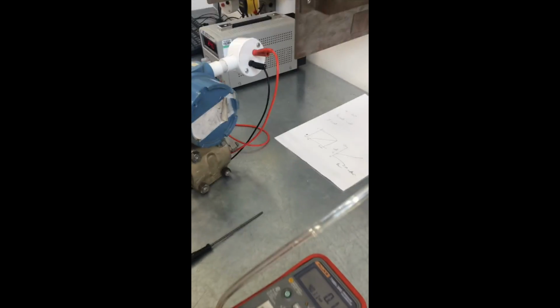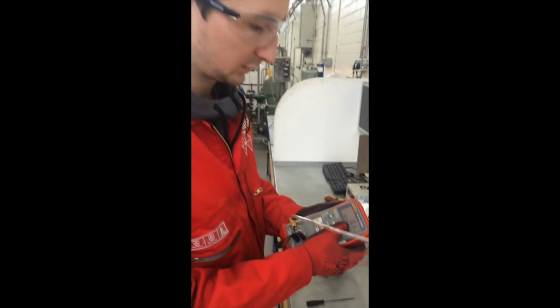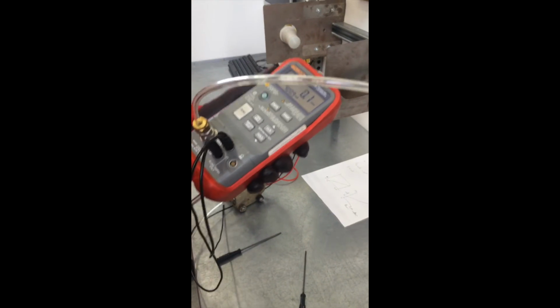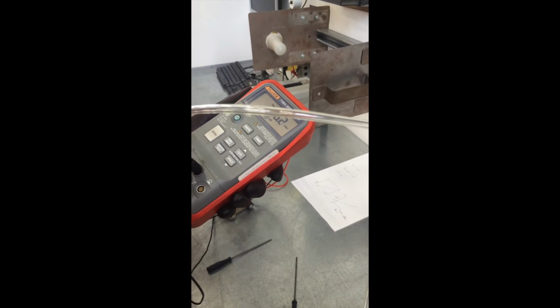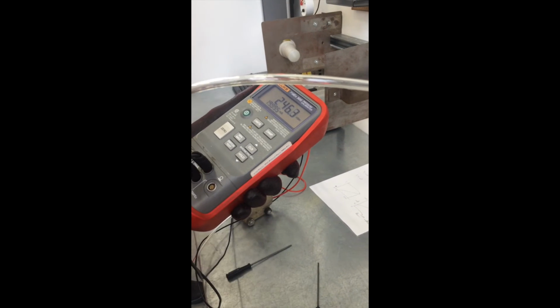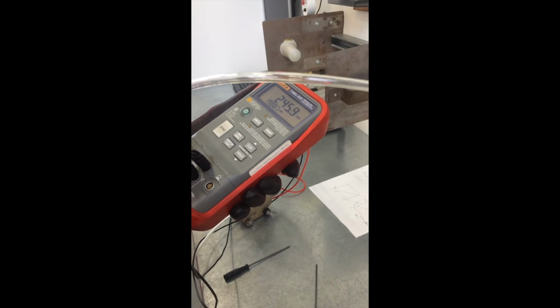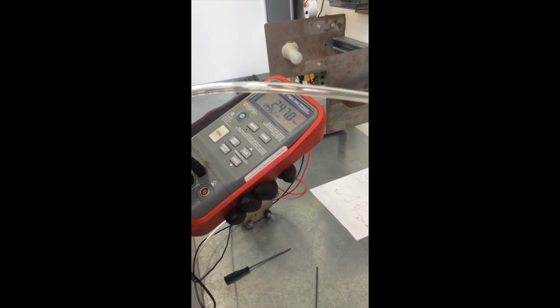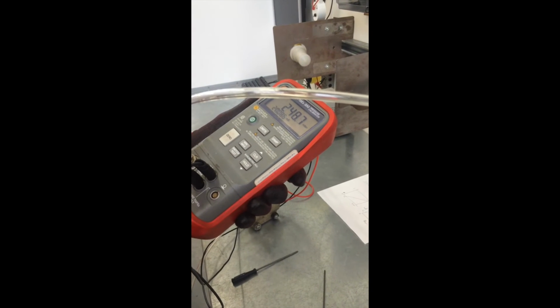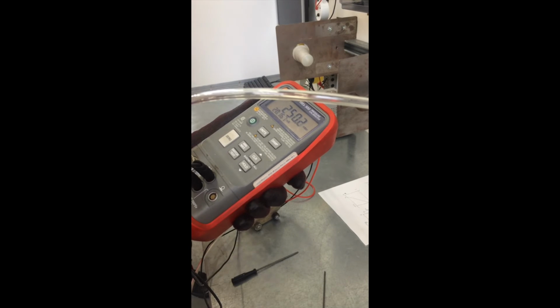Go, and that's it. First value is 0 at 4 milliamp. Once you've got the 0 millibar sitting at the 4 milliamp, you then pump your instrument back up to 250 millibar and just finally adjust it. So that's me sitting at 250, and that should be reading exactly 20.